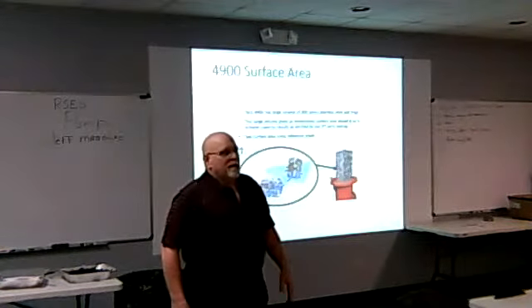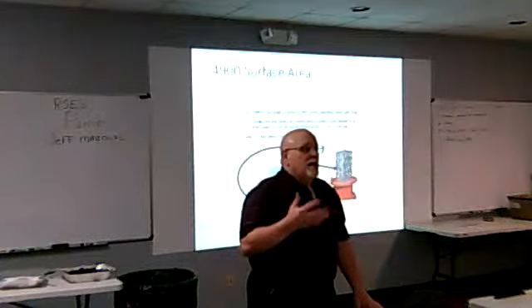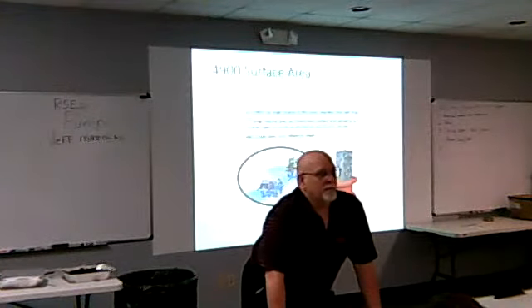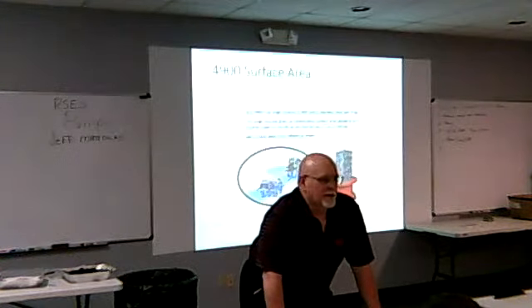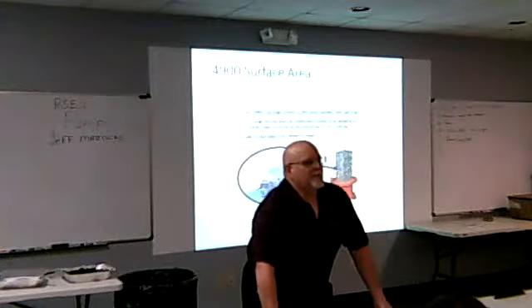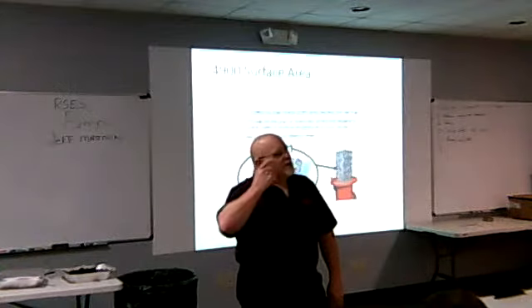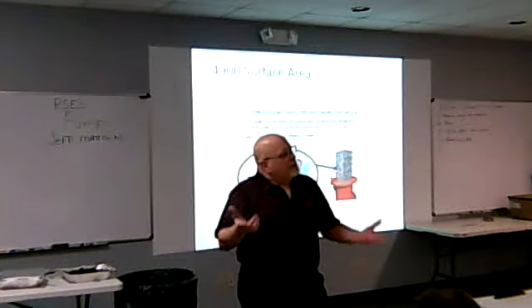Ball valves aren't the best, I mean, at 40% open you're 90% full, but every manufacturer of balancing valves uses ball valves. Flow Design, Griswold, Bell & Gossett, everybody's got ball valves. They do work really well. Butterflies work for balancing. You know, like Armstrong, they use globes for their bigger ones. Then you have to count the turns. But a butterfly does just as well. You know, for example, Flow Design.